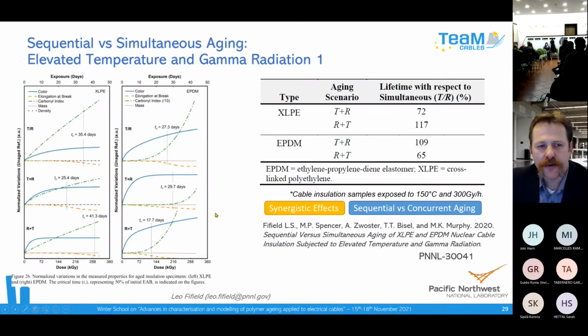Here we go. We similarly looked at the effect of gamma radiation and thermal stress as a function of the order in which they were applied to the material. We did thermal aging first and then radiation, or the other way around, or both simultaneously. Through different measures of aging, we saw that the lifetime of the cable material was affected by the order of exposure. Again, the take-home message was that we can't say all materials will age more quickly when exposed in a certain way. It turned out to be material dependent.